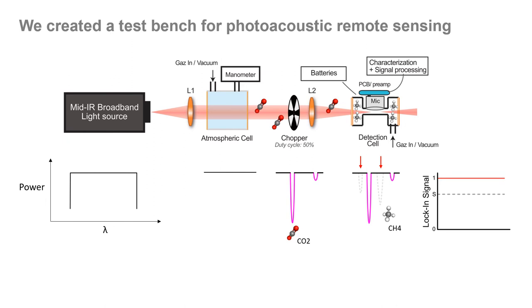To determine the concentration of the target gas in the optical path, or in this case, in the atmospheric cell, we only have to compare the acoustic signal previously produced in the detection cell to a calibration measurement with no gas in the atmospheric cell. The lock-in signal is then maximum, and we can retrieve the gas concentration by simply looking at the difference in acoustic signal.